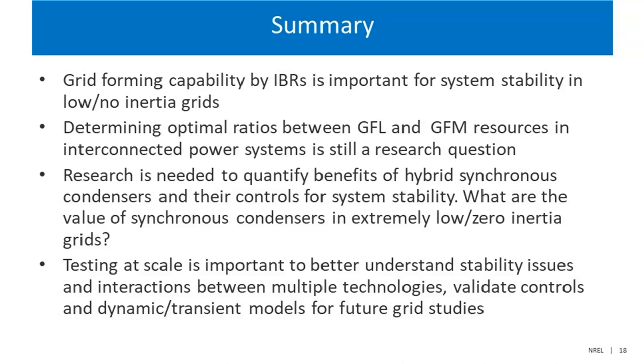Well, this is Ani again, if nobody else is answering. The distributed resources require distributed support, so I think it's a really good idea. The use cases I presented were more like a large transmission scale, but I believe for largely distributed resources, having synchronous condensers is very important for both voltage stability and also for short circuit current contribution, because it's an essential part of reliable protection operation. And the trade-off there is you either put synchronous condensers to provide short circuit current and operate protection in an old way, or you have to upgrade your whole protection, go into more advanced ways, communication-based or whatsoever. So I believe it's a good idea for distributed generation. Okay.